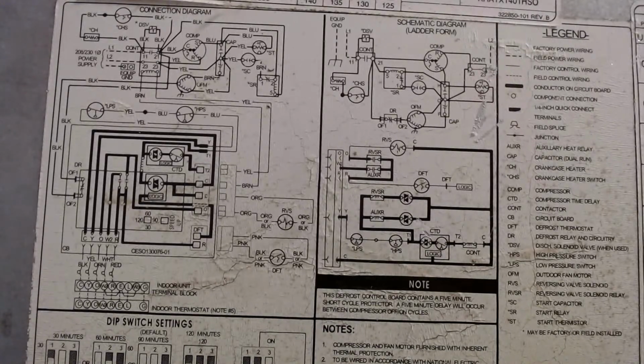But then we have our sensor wire, which goes through pink, hits our defrost timer thermostat, excuse me. And here's our drawn. See how it's drawn open. Everything is de-energized. So since it closes on a drop in temperature, you can see it's drawn open there. And it basically says, okay, once I've gotten cold to my set point of what the sensor set that closes at, it will close. And after our timer and our defrost board, our dip switch settings here, 30, 60, or 90 for your defrost is what it will go through. Depending on your region, your dip switches are what you need to set it for.